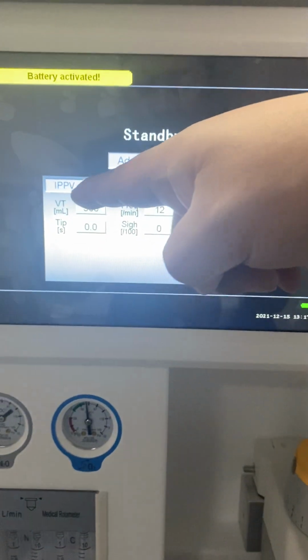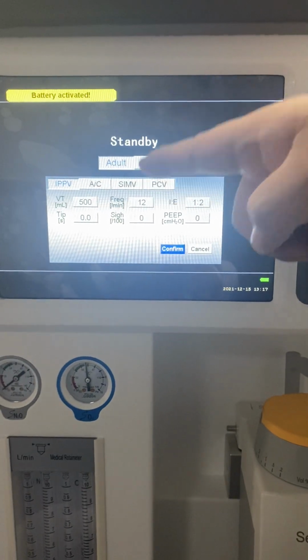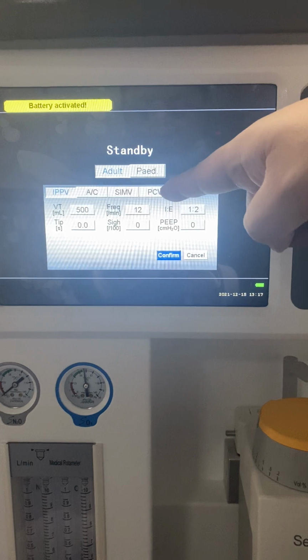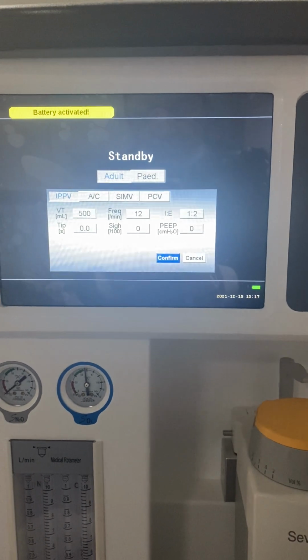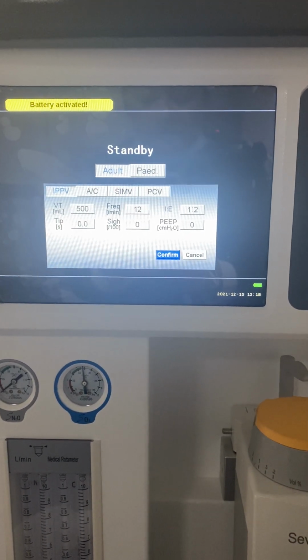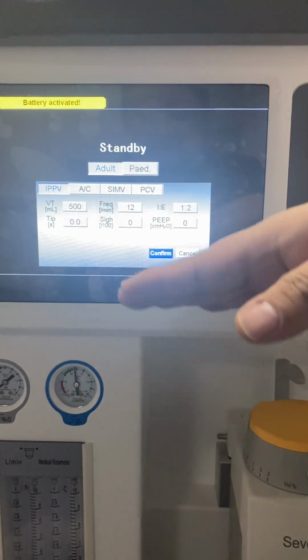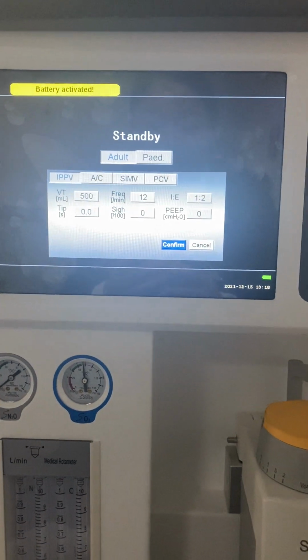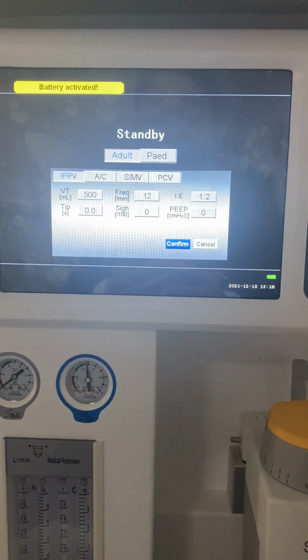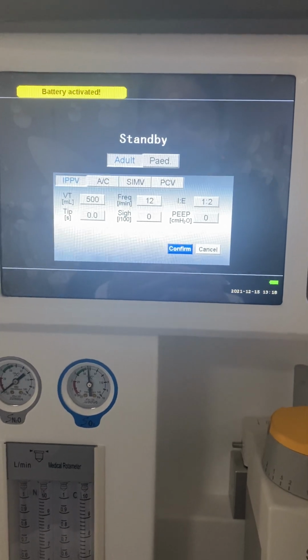Then we can set the parameters under each ventilation mode. For this machine, we have IPPV, AC and SIMV as volume control modes, and PCV as the pressure control mode. Also, if you like, we have PSV as an option. So this machine includes both pressure control and volume control, so it can be used for most kinds of patients.